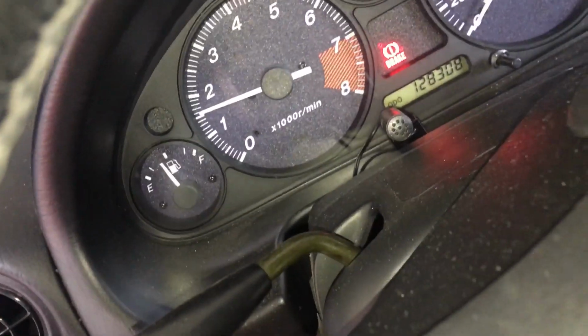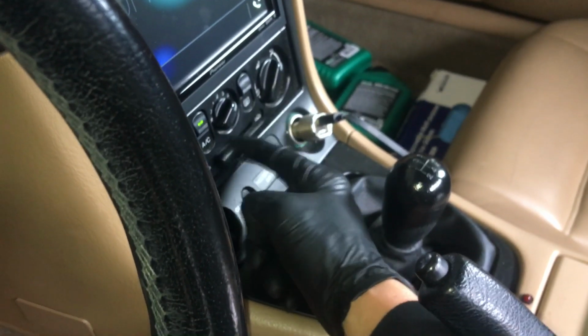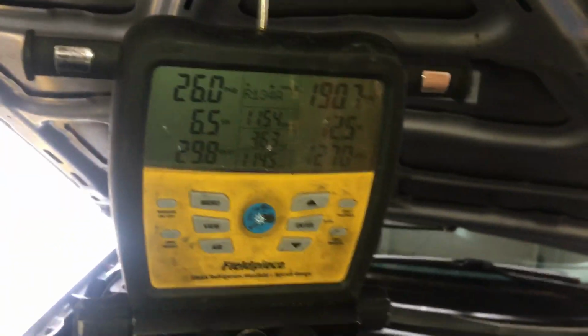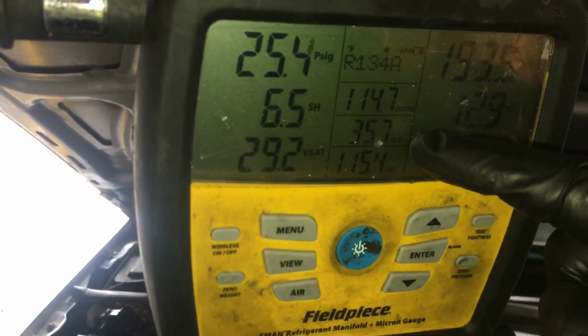So now let's throw it on recycle. Now we're at just over 1500 RPMs. So let's go over to recycle. So now I'm going to recycle this air inside here. That's like 50-some degrees. So now we're going to see the compressor start to short cycle, as you would say in HVAC terms. So now we're in recycle. Now look at our suction line temperature. It's going down. Now we're about to shut off.